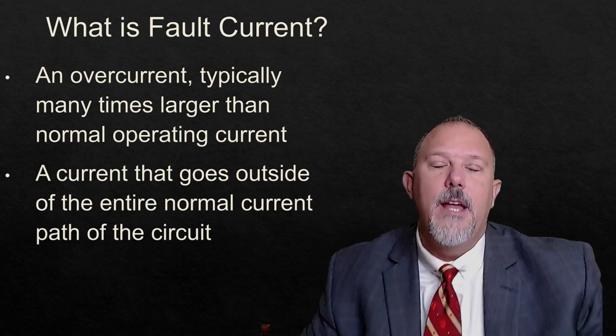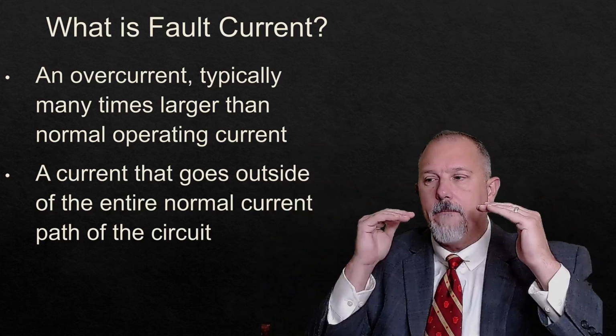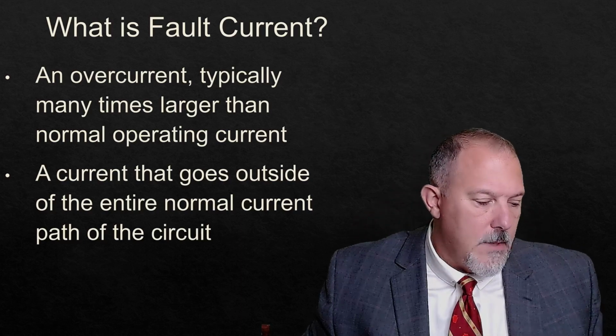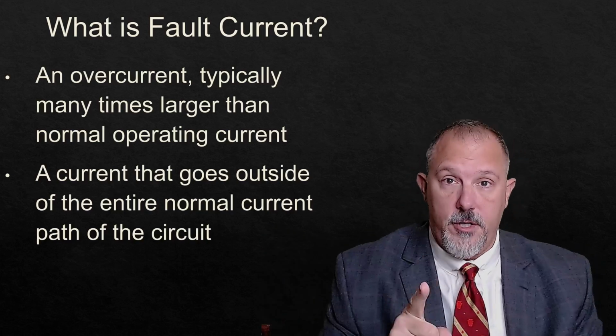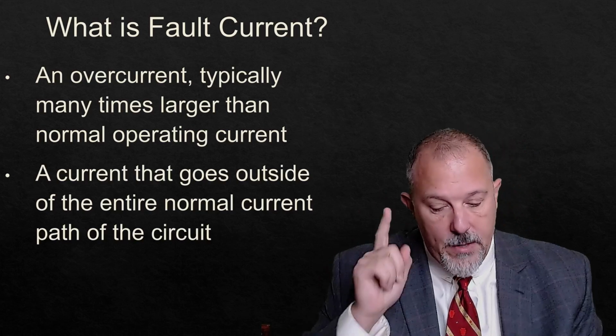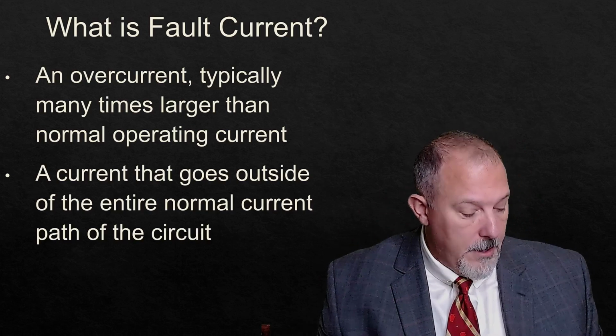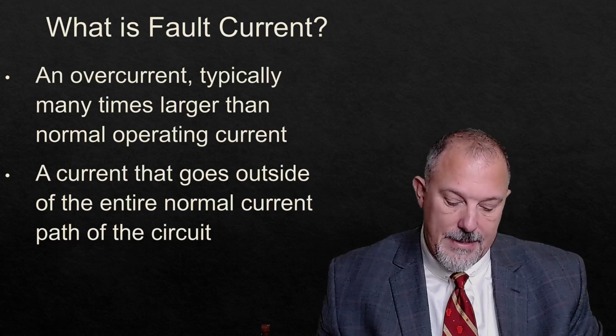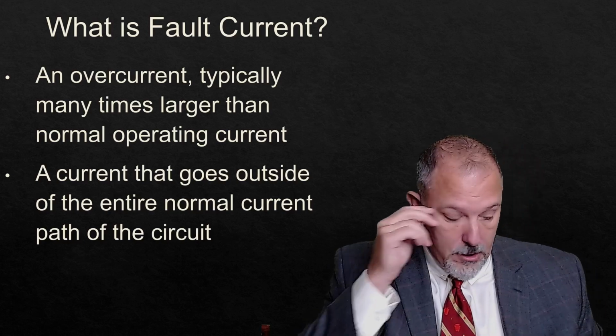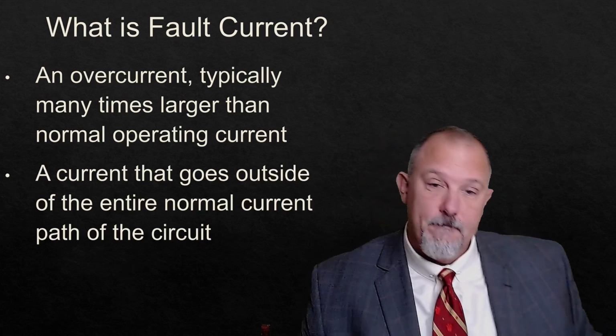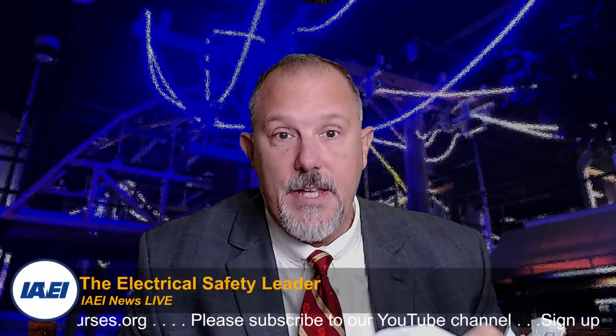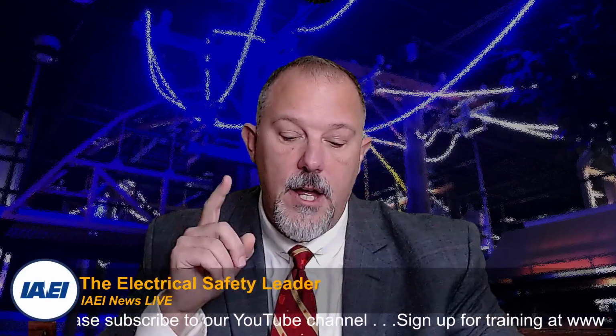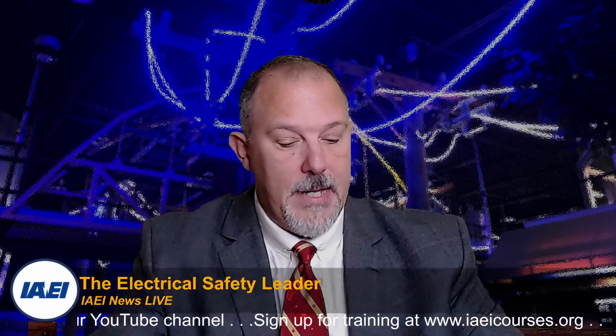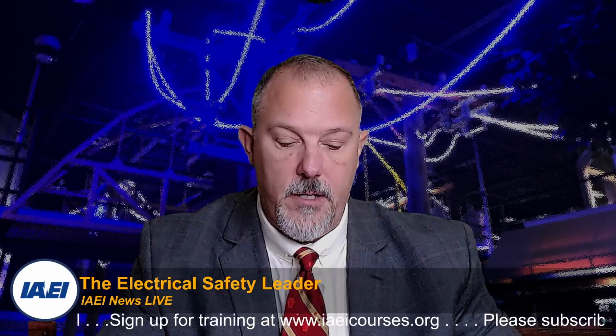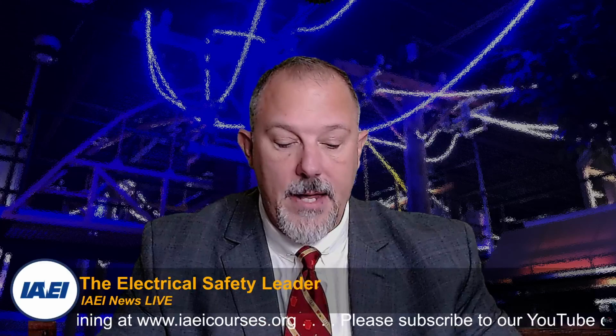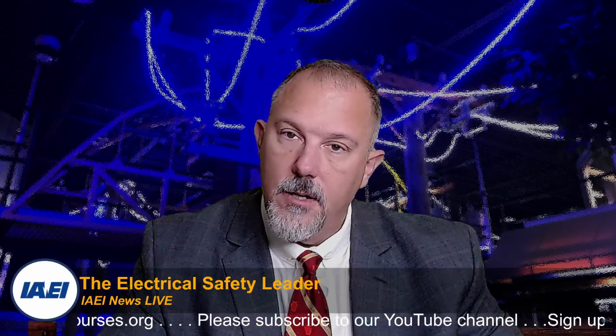Now, before we even get to the terminology, 30,000 foot view: what is fault current? Let's think about the definition of overcurrent. I don't have this in my slide deck, but if you have your code book, go to your 2020 version of the National Electrical Code, element O, overcurrent, page 38. Let's take a look at the definition of overcurrent. It says any current in excess of the rated current of equipment or the ampacity of a conductor. It may result from overload, short circuit, or ground fault.